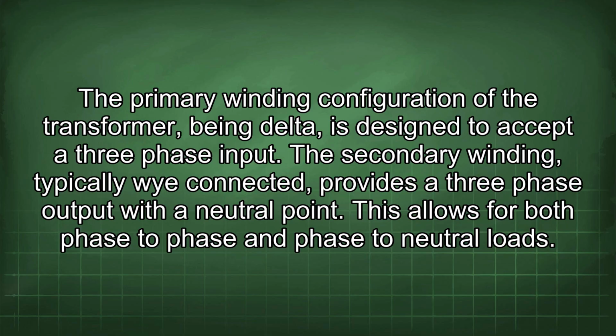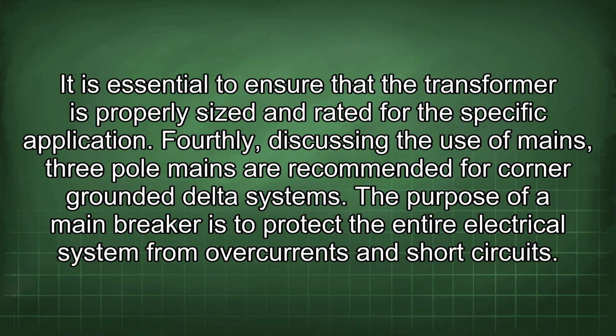The primary winding configuration of the transformer, being delta, is designed to accept a three-phase input. The secondary winding, typically Y-connected, provides a three-phase output with a neutral point. This allows for both phase-to-phase and phase-to-neutral loads. It is essential to ensure that the transformer is properly sized and rated for the specific application.